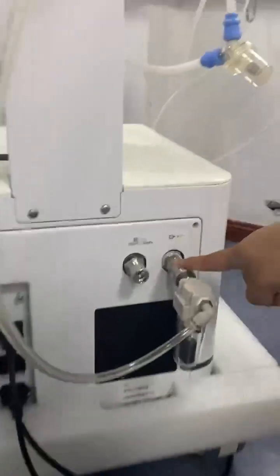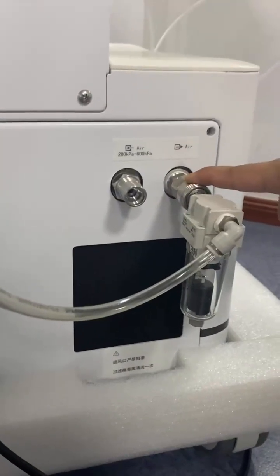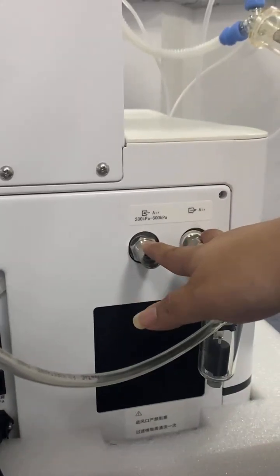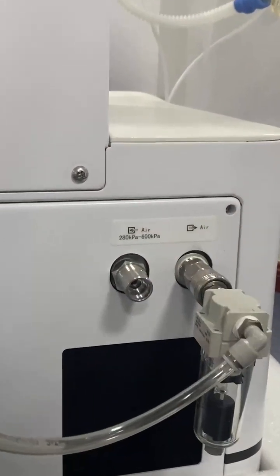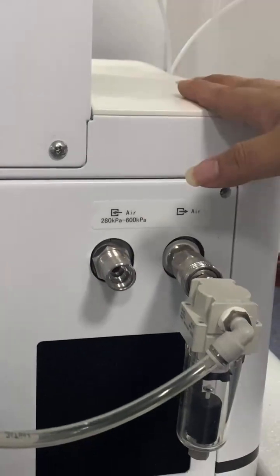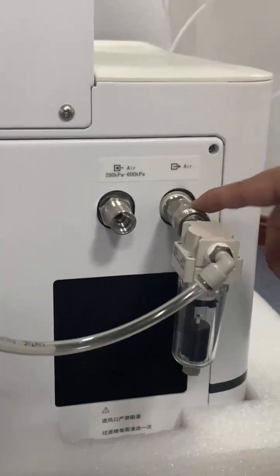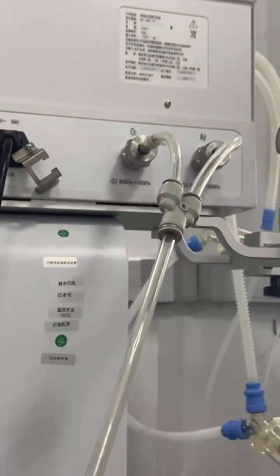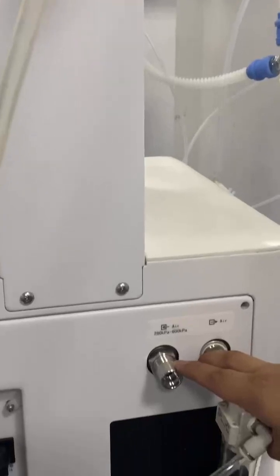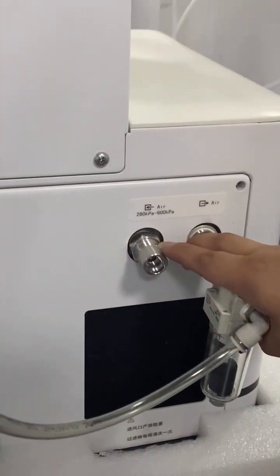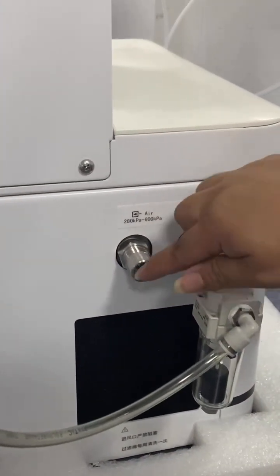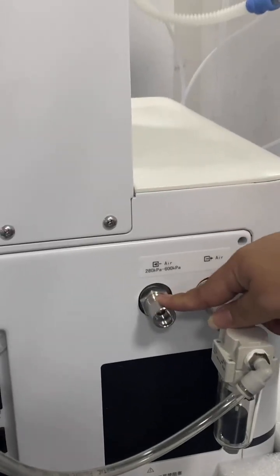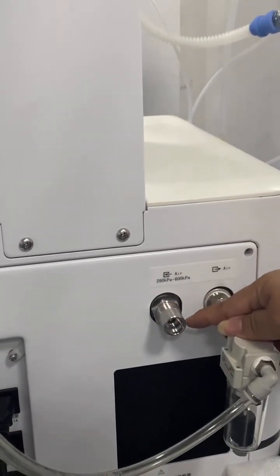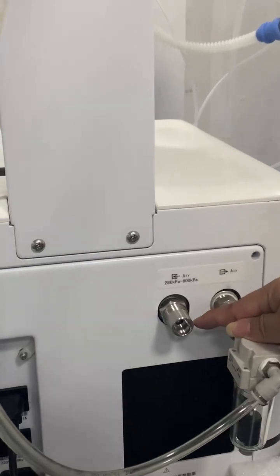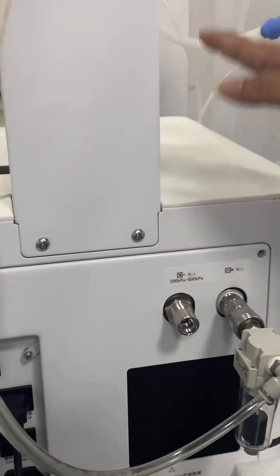And then we will see the air inlet, the gas source. You can see there are two air gas source ports here. So why are there two? Because it's also an advantage. As we already have the air compressor, we can connect one side to this port and the other side to our air compressor. If your hospital has a central air supply or you have a medical air cylinder, then we can connect another line from here to your central air supply or your medical air cylinder. Then it means you are connected to two air sources: one is your cylinder or central air, and the other one is our air compressor.